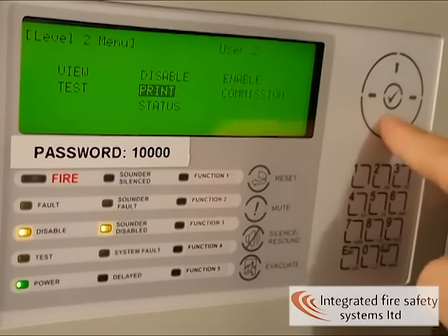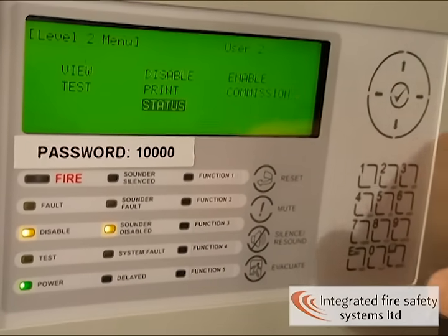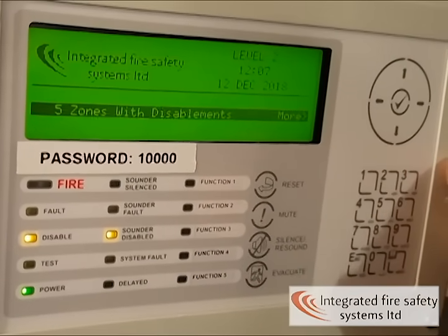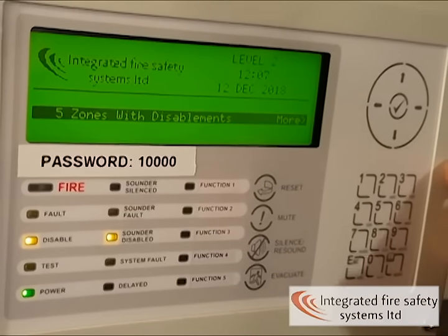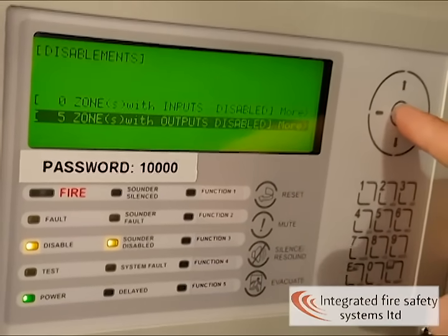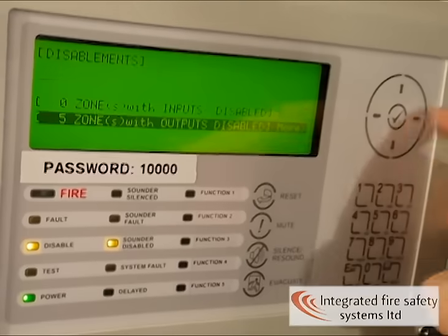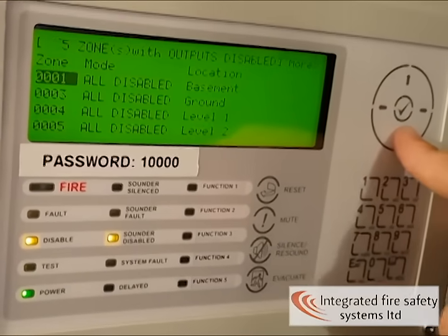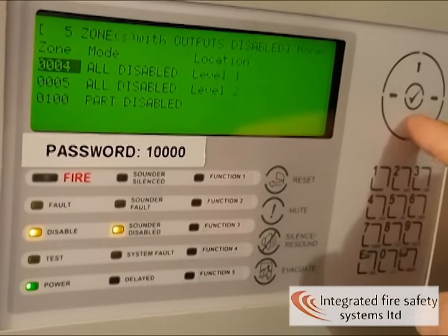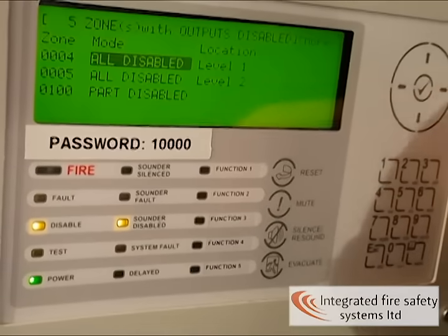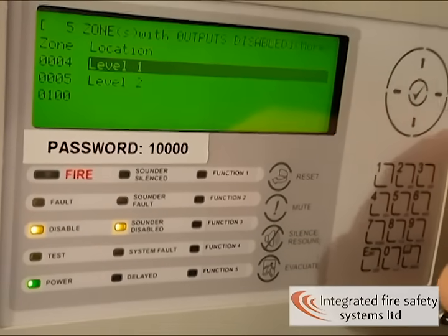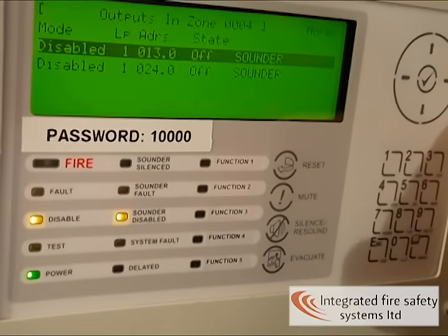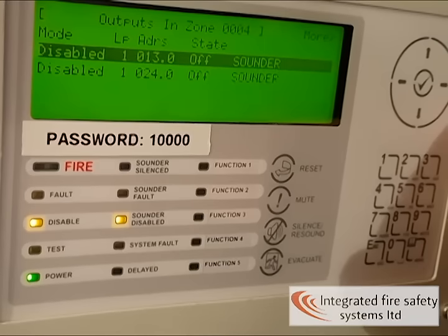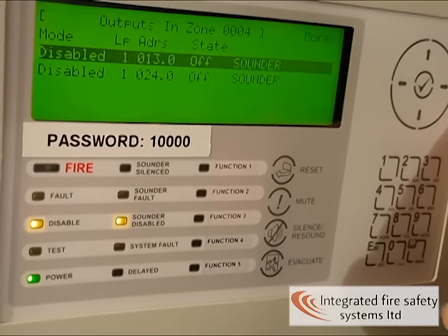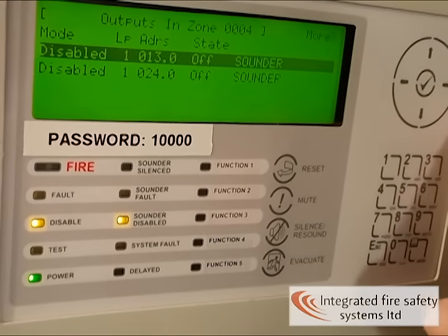Select down to go to status. When you're viewing the status of the panel, it will show you any disablements that are present. If you press right and continue to press right, you can drill down to see exactly which devices are disabled. You can re-enable these once you're in user level 2 by going to enable. This will then show you exactly which devices are disabled, and you can then click on them to enable them.